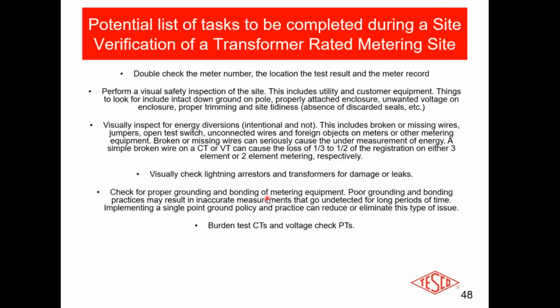Performing a visual safety, okay? You're looking for the intact ground. The enclosure is attached. How many times have you gone up and the only thing seeming to hold up the wall is the enclosure? Unwanted voltage, proper trimming, site tidiness, stuff that's gotten into the cabinet, animals or otherwise, water in the bottom of it, etc. Always assume you always walk up with your PPE on because that box could be live. There could be a short in there.